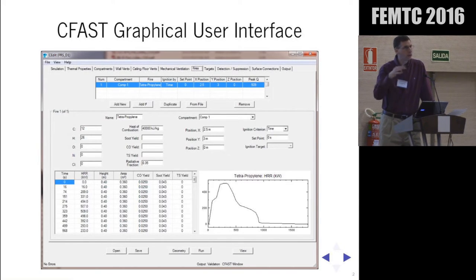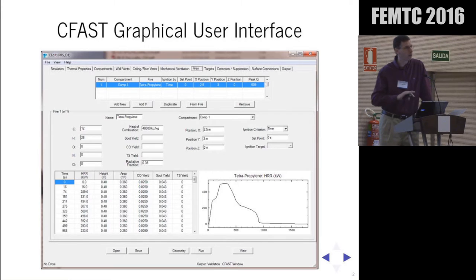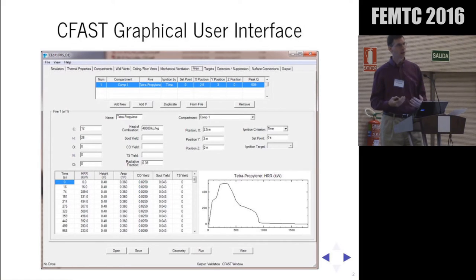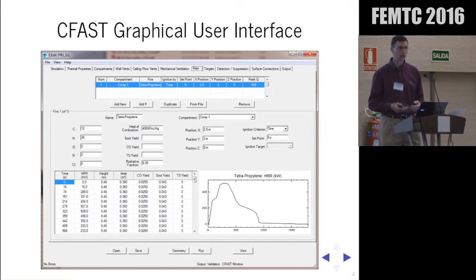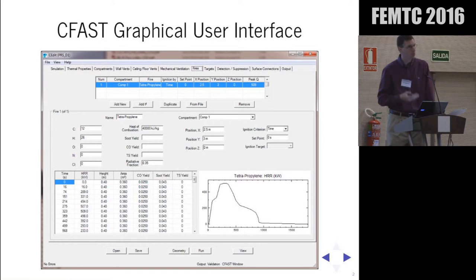As I started digging myself, what I found was a bit shocking. A lot of you may assume that the basic concepts of flow through doors and hatches — the basis of zone models — are so well known and well understood. Yes, it is well understood, but when you actually go to code it up and make all these empirical correlations work together, there's a lot of stitching together that goes on. It was people like Rick Peacock, Paul Reneke, and Glenn Forney who did all that. For instance, the Heskestead plume and the Alpert ceiling jet don't meet at the centerline — what do you do there? They said they just split the difference. Has that ever been validated? No. Has anyone really looked at it closely? No.